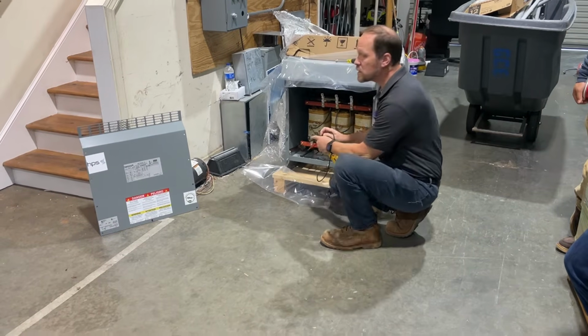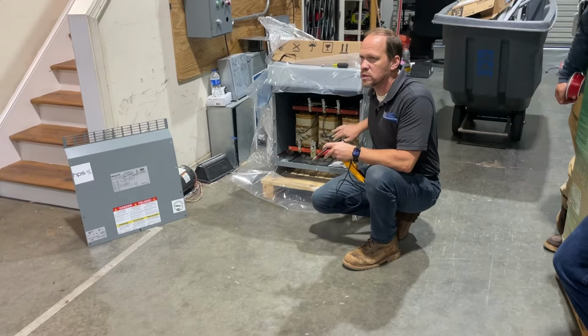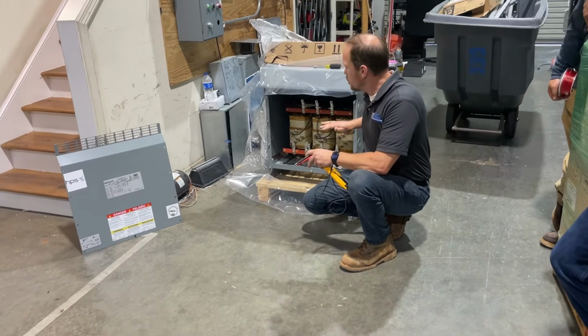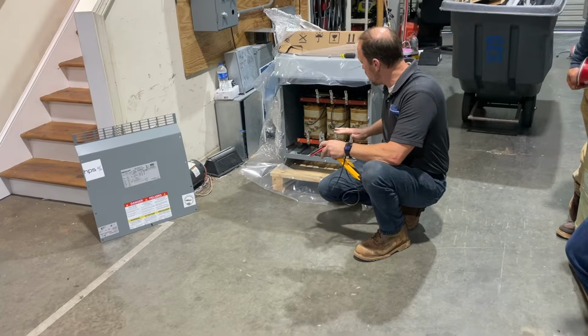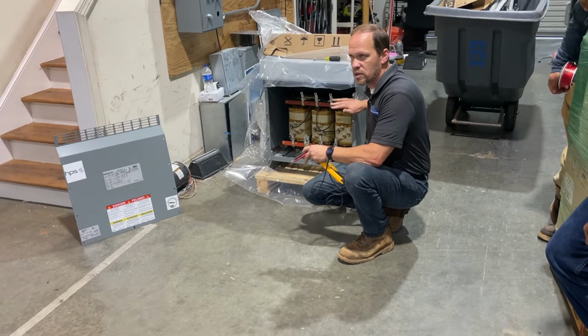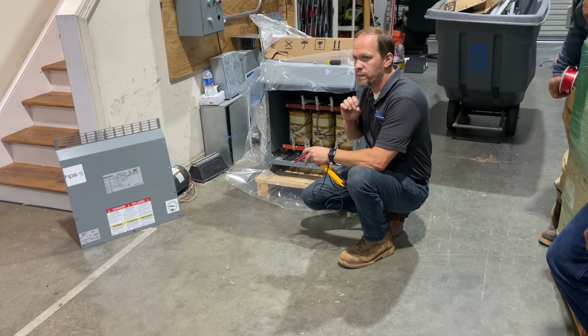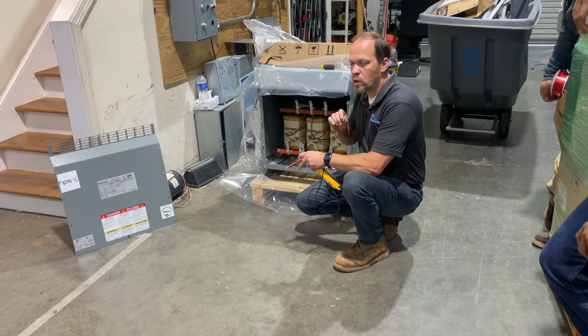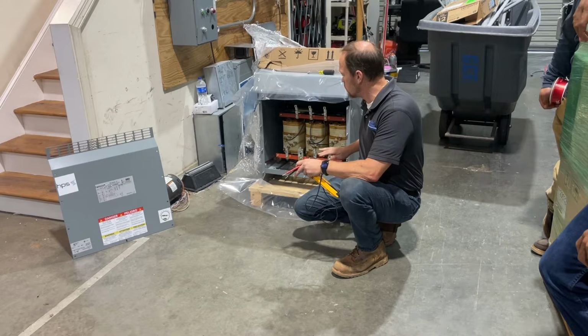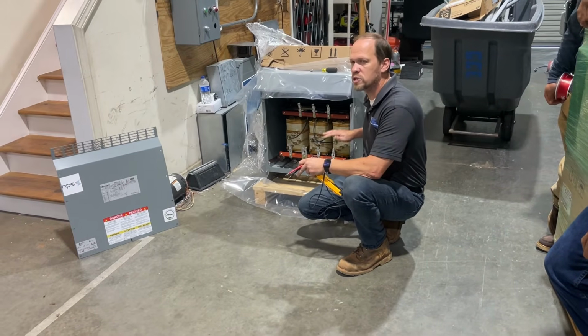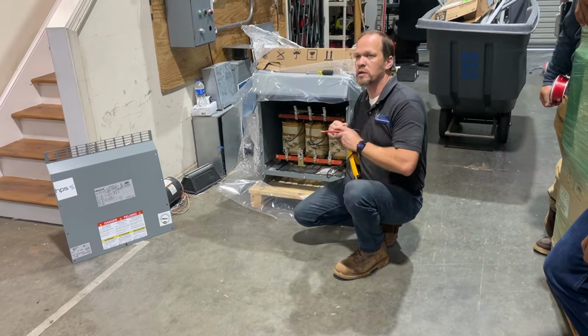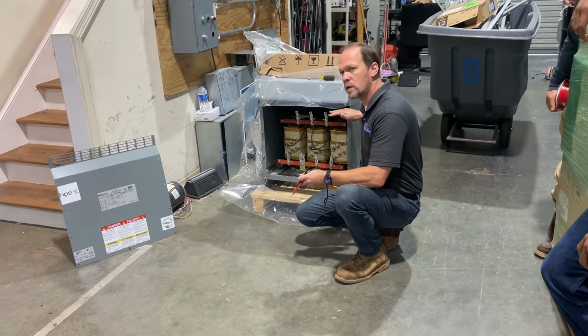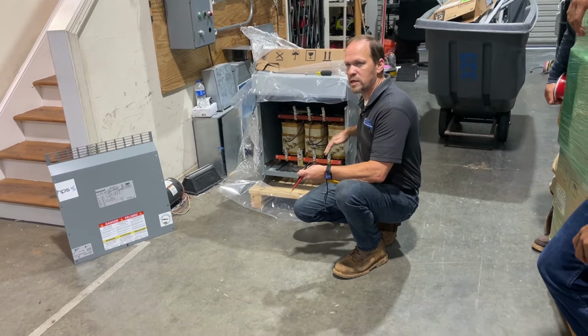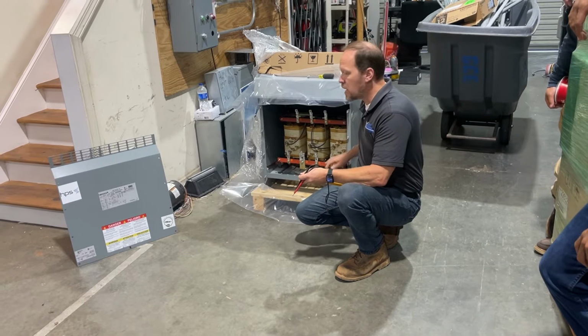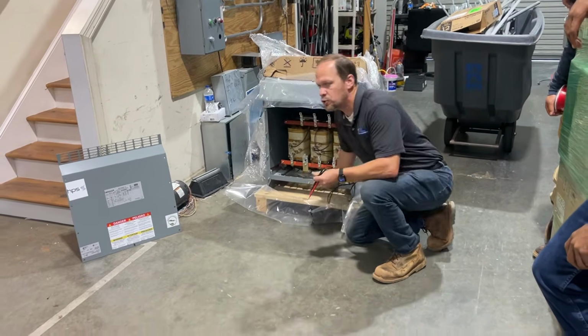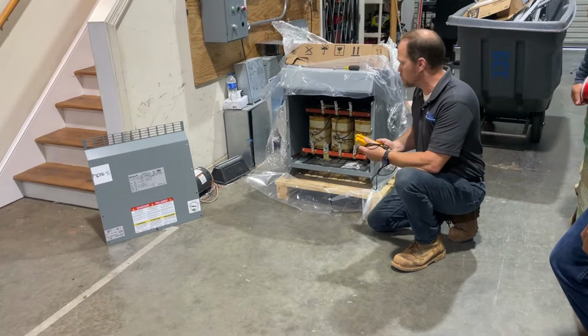tripping. There is no physical connection in this kind of transformer. This is a dry type standard transformer. There is no physical connection between the primary side and the secondary side. Zero. No physical connection. Just a real quick side note, sometimes they'll use a transformer that goes from 240 to 240 or 480 to 480 as a surge suppressor, because the voltage spikes that come on this side will have no physical connection to the other side. And it will actually absorb that spike. So sometimes an isolation transformer can be used as a transient voltage surge suppressor.